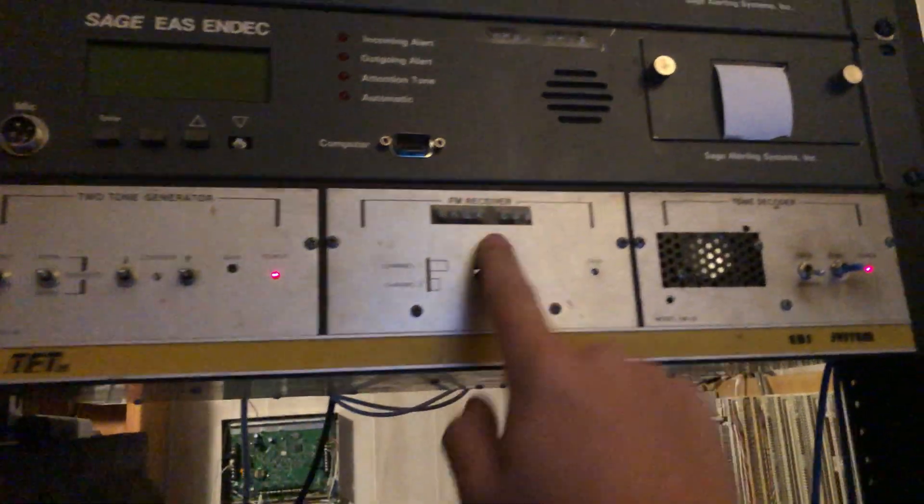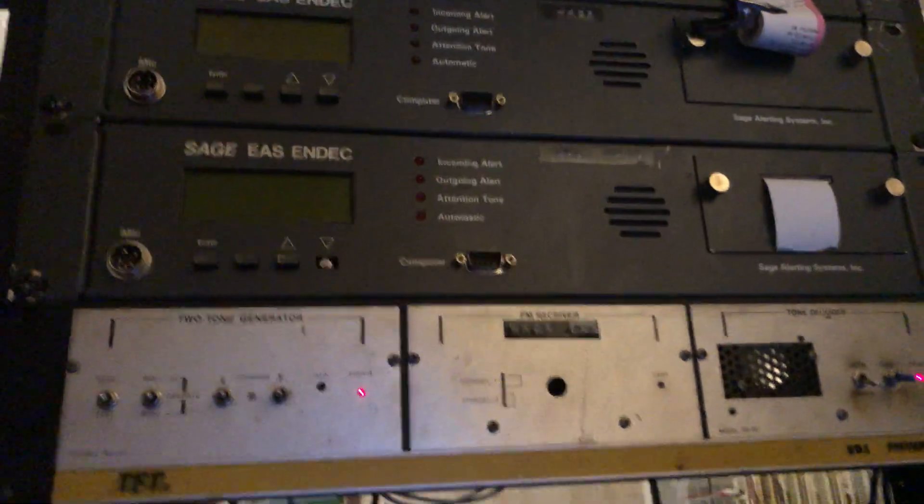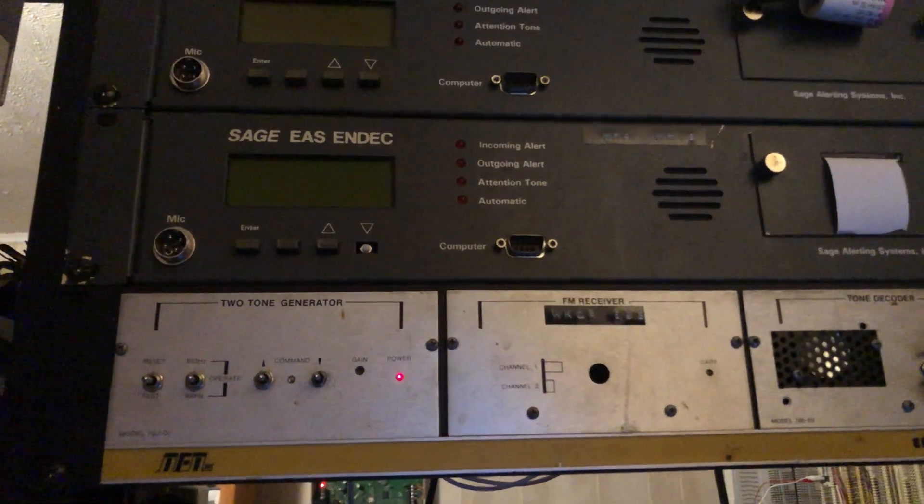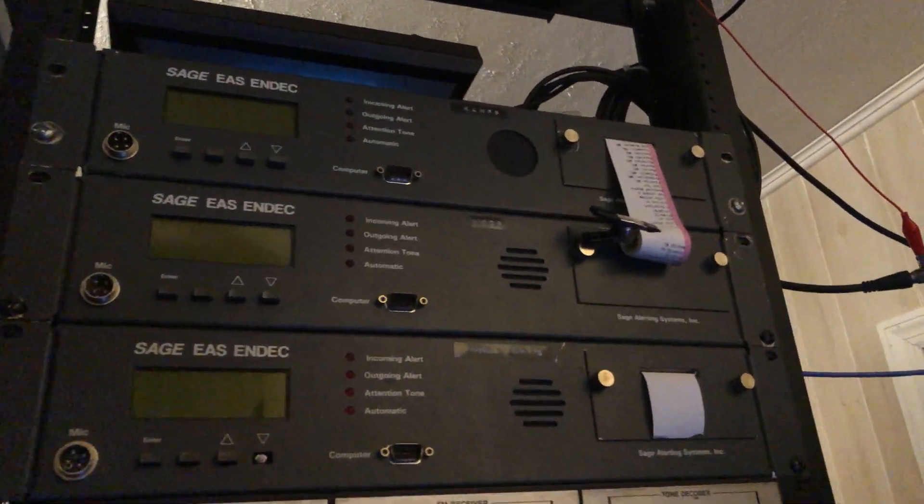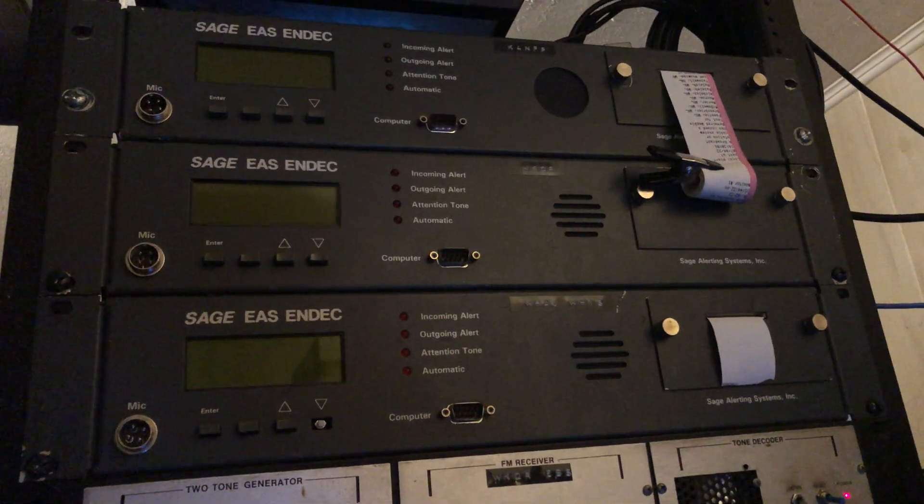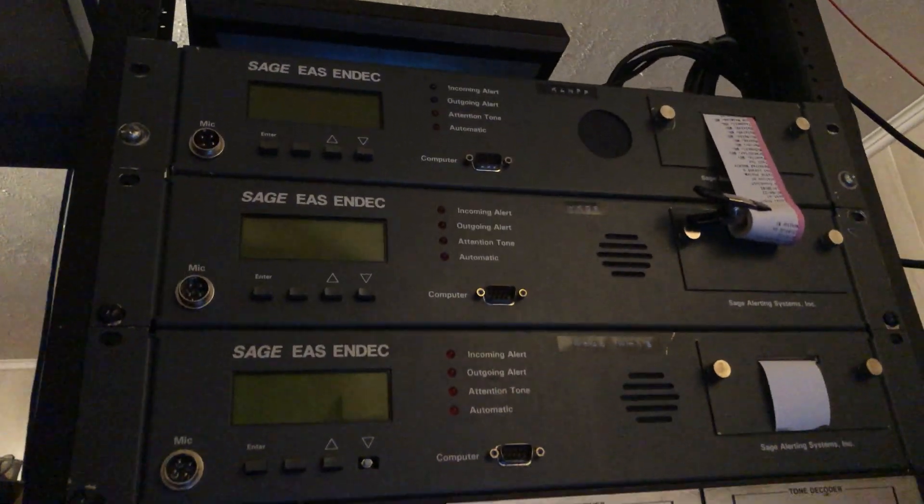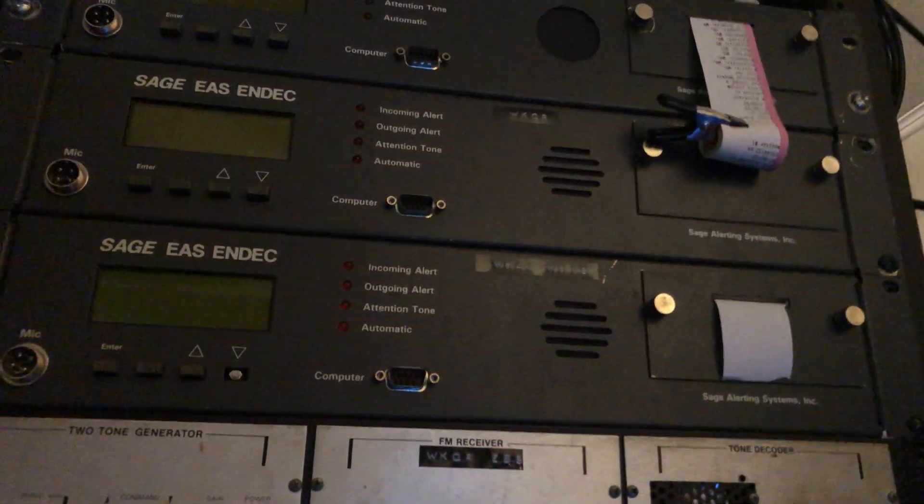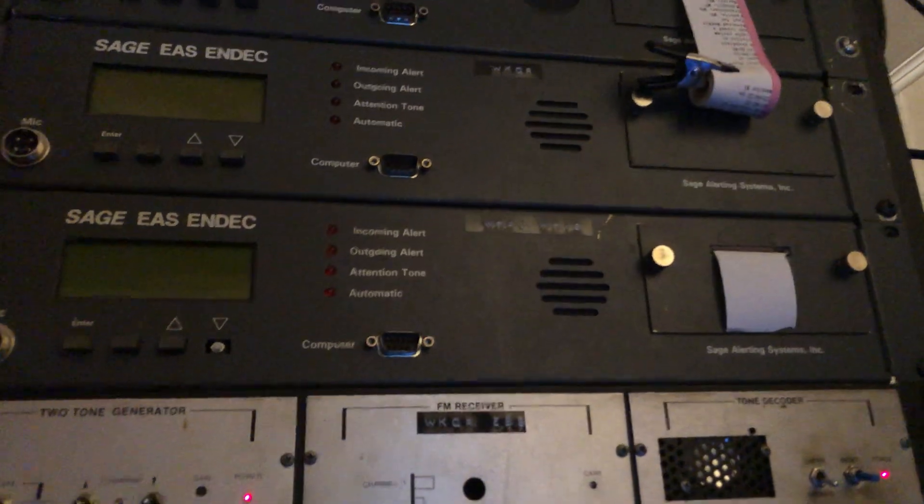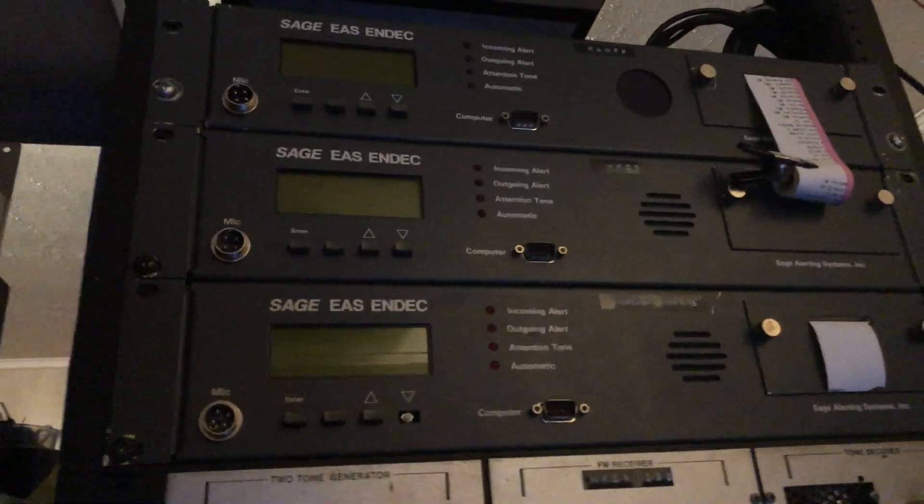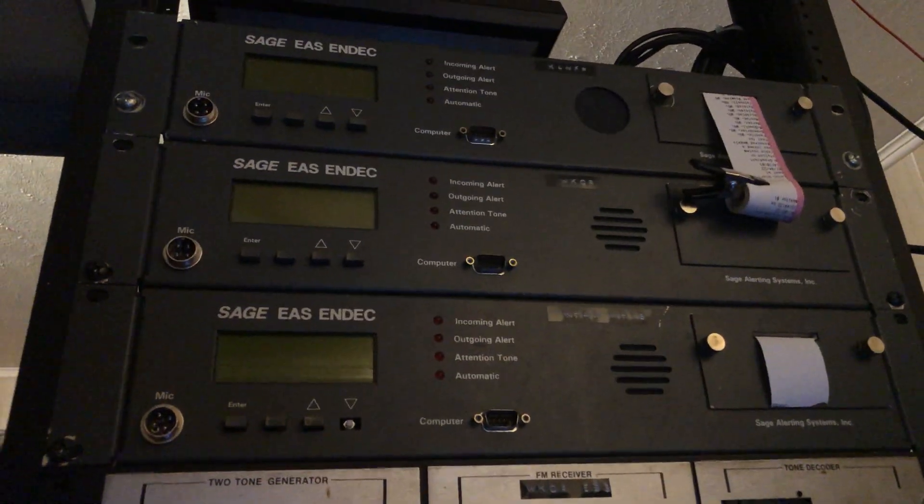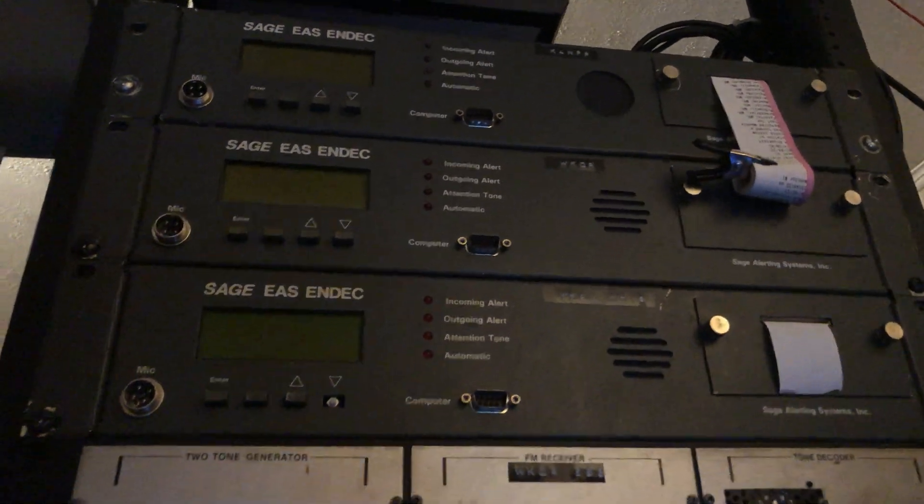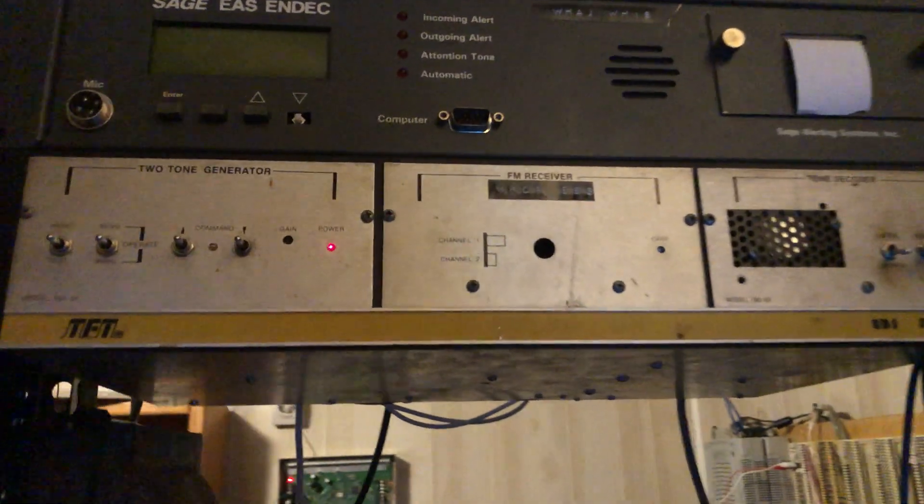Well, when you have your entire radio system automated except for your EBS system, you got problems because if you got to have somebody there just to listen for an EBS, you can't do that. So basically what they did is they moved on from the EBS system and they made the EAS system, the Emergency Alert System, that used the same tone for an attention tone, not to actually trigger things but as an attention tone to get somebody's attention. And then they used FSK, frequency shift keying or audible frequency shift keying, to actually incorporate the data into the alerts and automatic message recording.